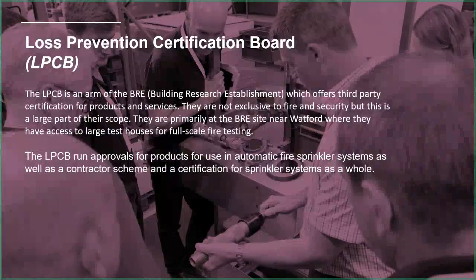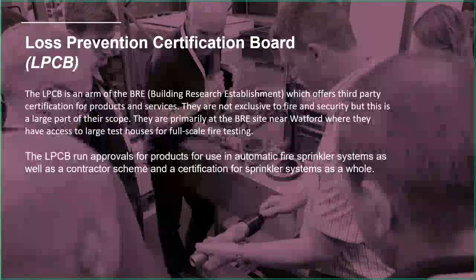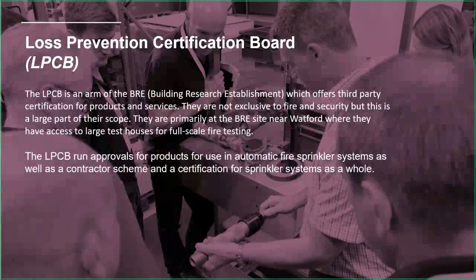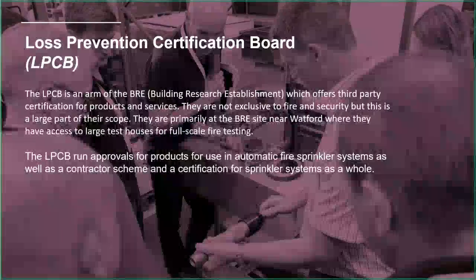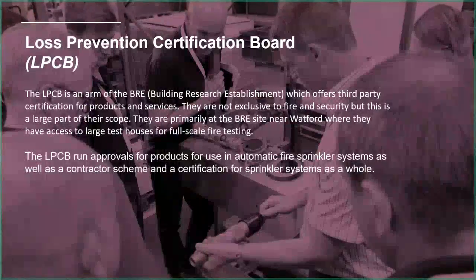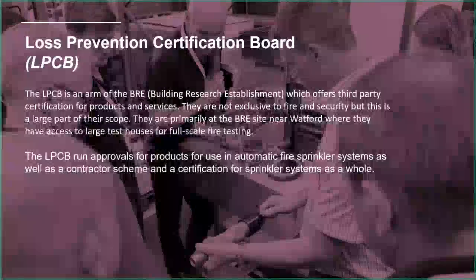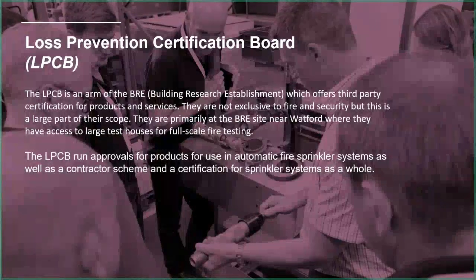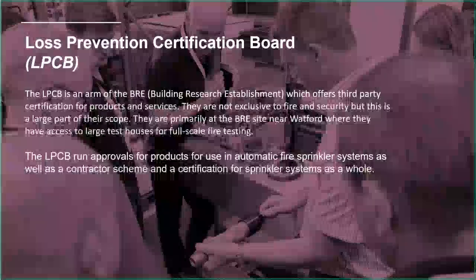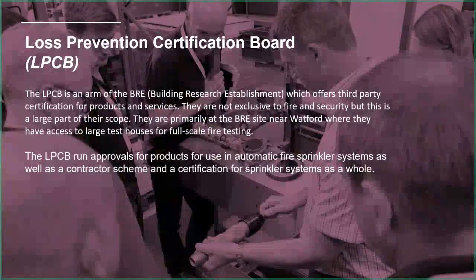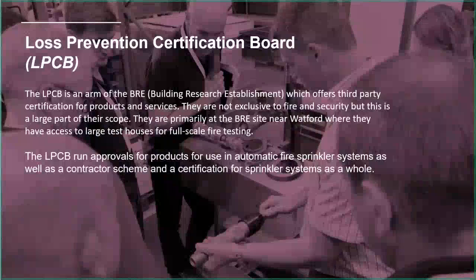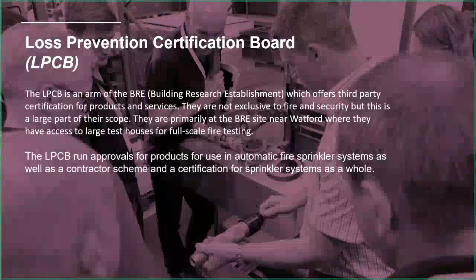They're primarily based at the BRE site, near Watford, where they have access to large test houses for full-scale fire testing. That's obviously important, particularly when approving sprinkler heads. They've got big warehouses which they can partition off, put false ceilings in, and conduct full proper fire tests where they actually set fire to things with a known fire load, testing the effectiveness of the sprinkler heads discharging water at different pressures. So they are set up to do that kind of full-scale testing.